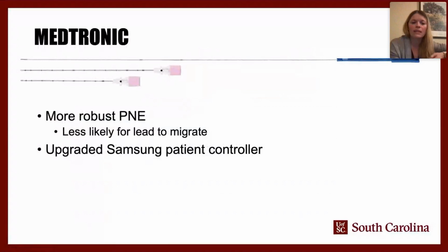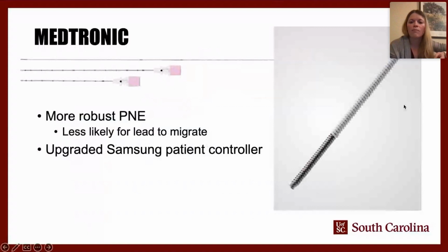So the PNE lead, they made it more robust, and it has this coil style to it with a single electrode at the tip. The advantage is that once this lead is placed through your needle, the electrode at the tip is less likely to migrate with this design, because if the lead has any tension on it, it will start uncoiling, like a slinky, and the tension will be released by uncoiling the lead without actually moving the tip of the lead.